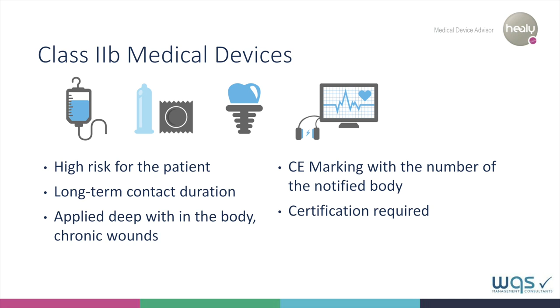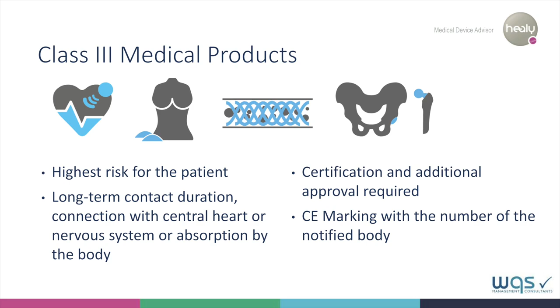Class 3 products have the highest risk class and the longest duration of application. They may be implanted into or absorbed by the body. Good examples for Class 3 devices are pacemakers or artificial hip joints. In addition to the certification, as in Class 2A and 2B, Class 3 devices need approval as a medical device. Let's now move on to the so-called conformity assessment procedure.